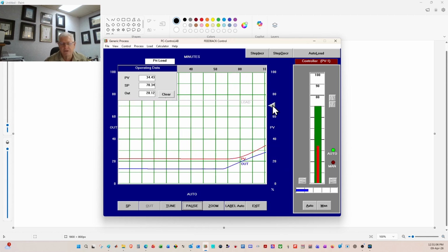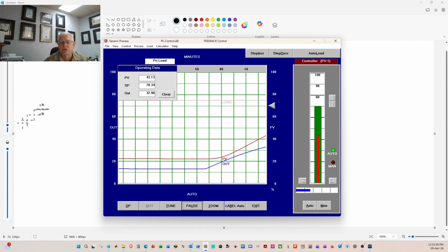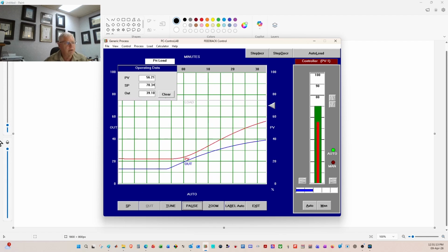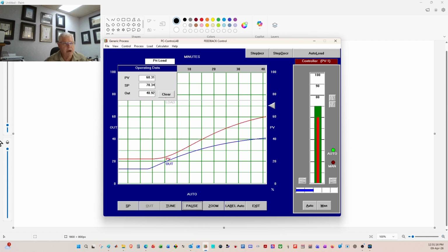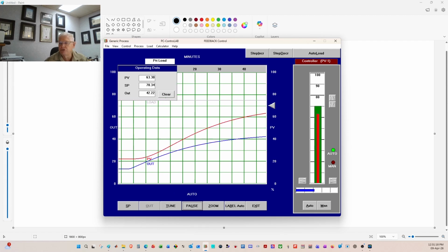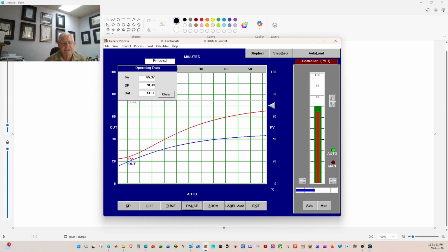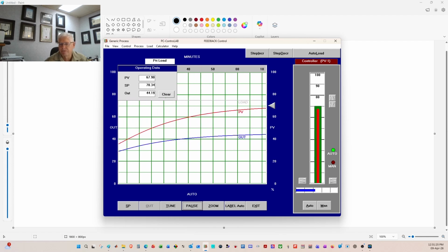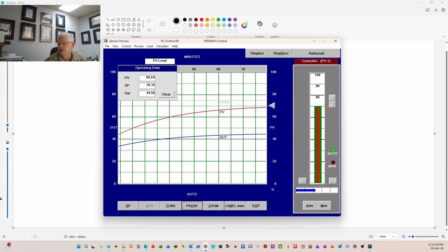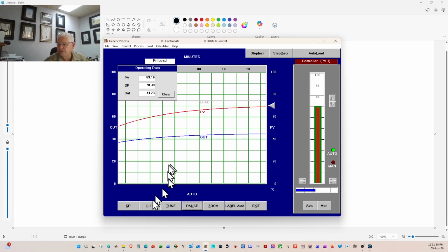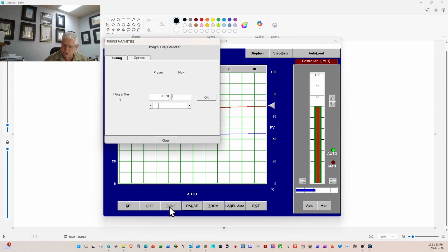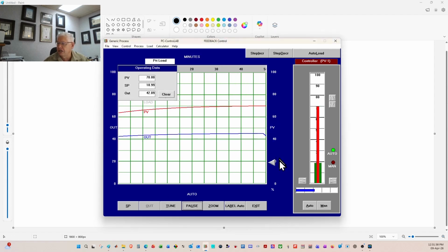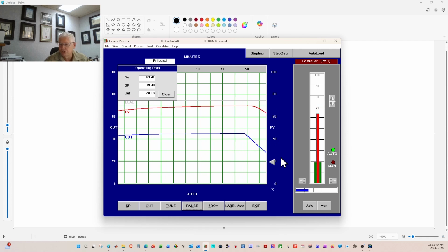You can actually see the rate of change of the blue pen is increasing. Once again, I'm going to just allow it to self-regulate, which is round about now, and you can see how the red pen is approaching the set point. Nice and stable control. Almost there, just going to let it go a bit further. Great. Okay, I'm going to increase the speed of it by changing that tuning parameter to 0.04, and if I do exactly the same, you're going to find that the system will respond quicker.